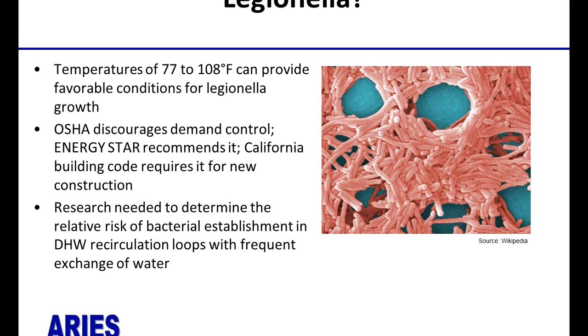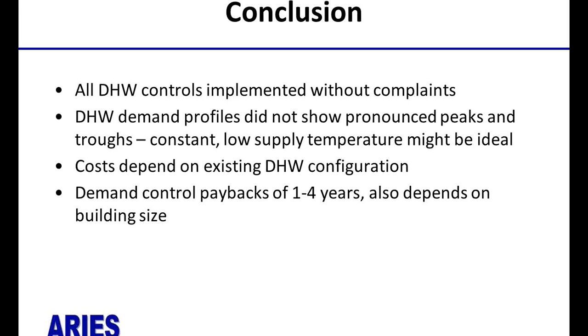Finally, a word about Legionella. The temperatures that favor Legionella occur probably in every DHW system at some point on a branch or a dead leg. And we're not sure if doing demand and temperature modulation controls, in cooling the recirculation loop or in cooling the tank temperatures periodically, poses a risk or if this exacerbates that. Now, government agencies are split on the issue, with OSHA discouraging demand control specifically. Other agencies require it. And more research is needed specifically on domestic hot water systems.